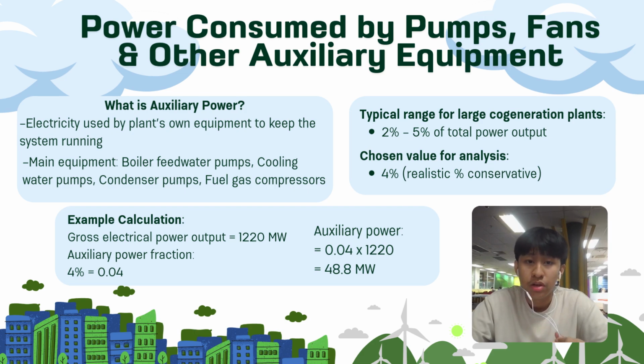So for an example of calculation for this part, the gross electrical output equals 1,220 megawatts, and the auxiliary power fraction is 4%, which equals 0.04. So auxiliary power equals the auxiliary power fraction times the gross electrical power output, which is 1,220 megawatts. So the auxiliary power obtained by the calculation is 48.8 megawatts.